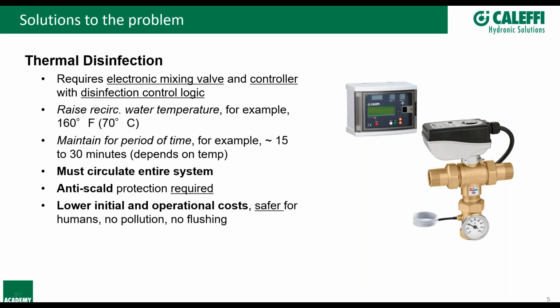Now, the things you need to watch out for with thermal disinfection: you need to circulate as much of the system as humanly possible. As engineers, designers, installers, you're all well aware you're trying to keep your dead legs as minimal and as small as possible. There are codes in certain areas that say you have to be no more than 2 feet away from the fixture with your recirc tapping, or within a certain amount of time to get it there, depending on what you want to do. But the idea is you want to completely get rid of dead legs as much as possible.